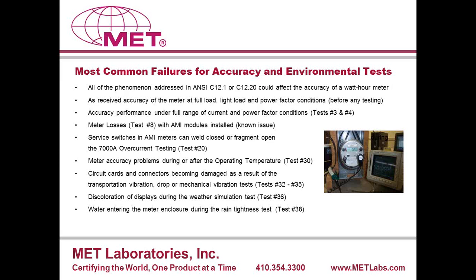The most common failures that I see in my lab, I'll let Monsi talk about the EMC failures, but what we typically see in the accuracy lab and running the environmental simulation tests, we see some of these. It's not in any particular order. Any of the tests could fail, of course. Any of those applicable 38 tests could fail. But I talked about it just a bit ago, the full load, light load, power factor failing right in the beginning of the test program or before or after any of the tests are performed. We see that quite a bit during the course of the test program.